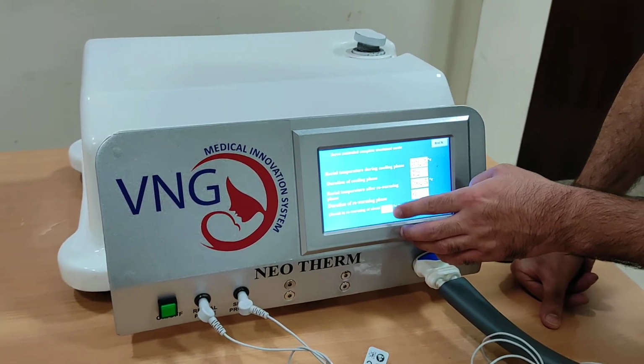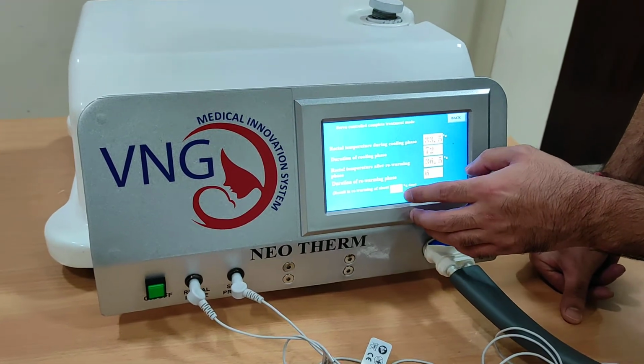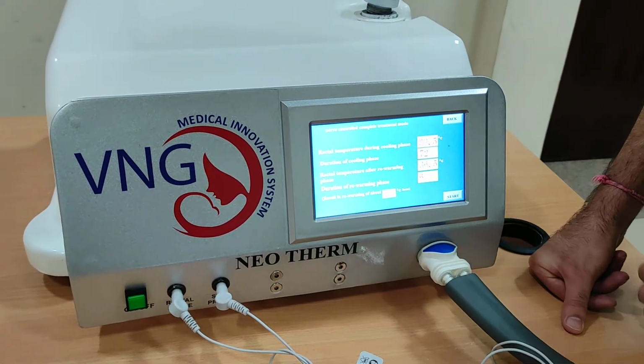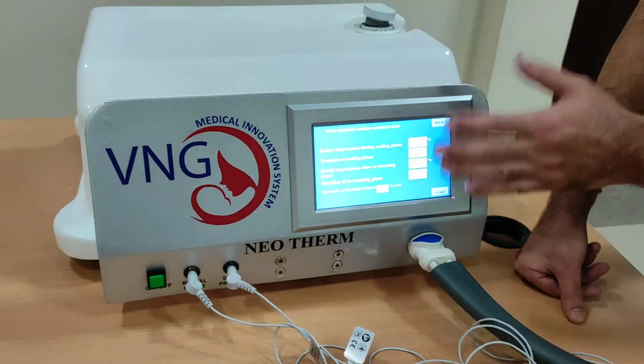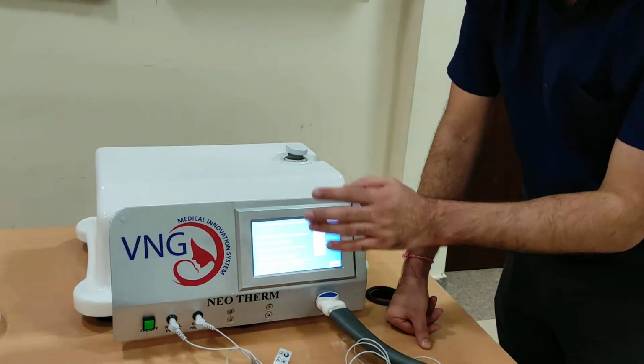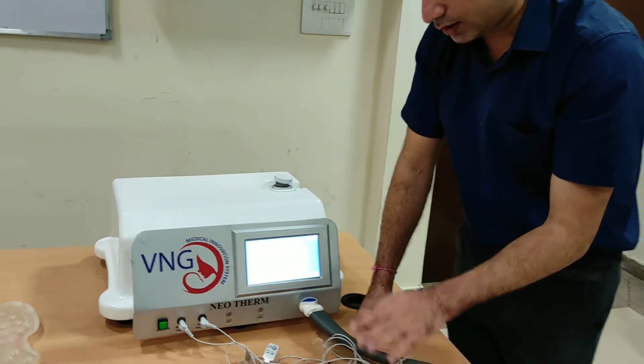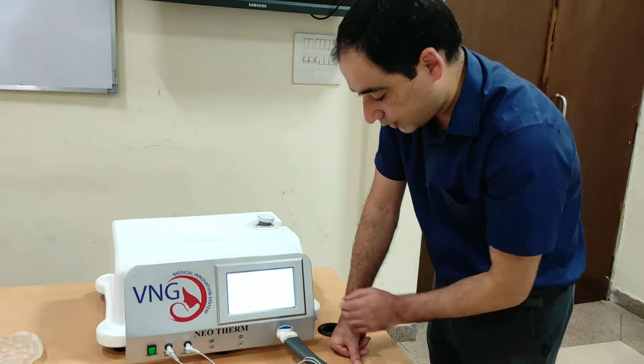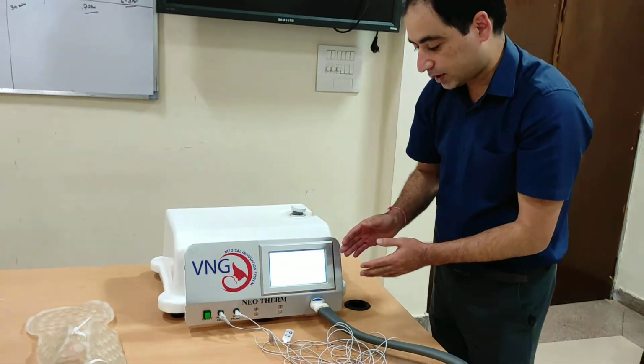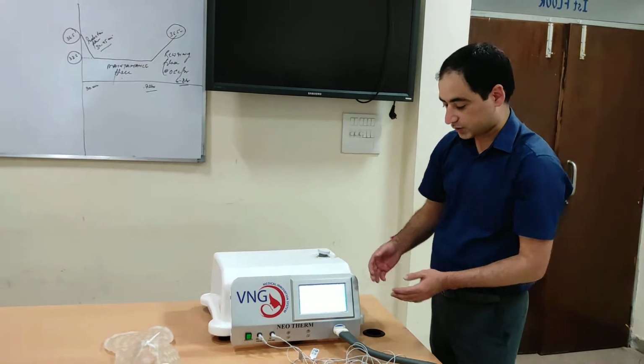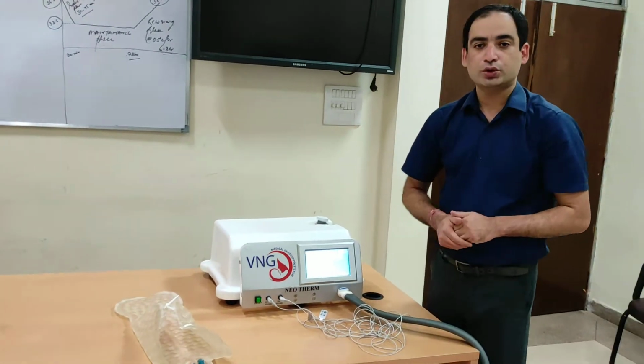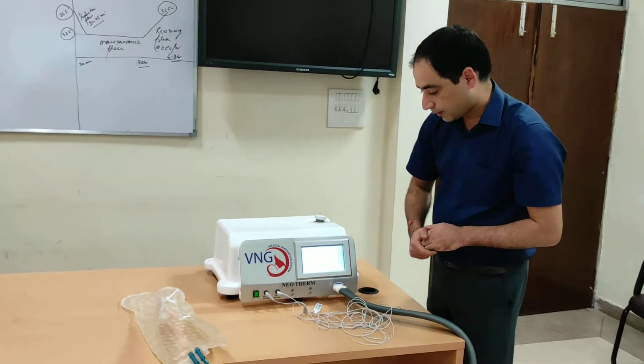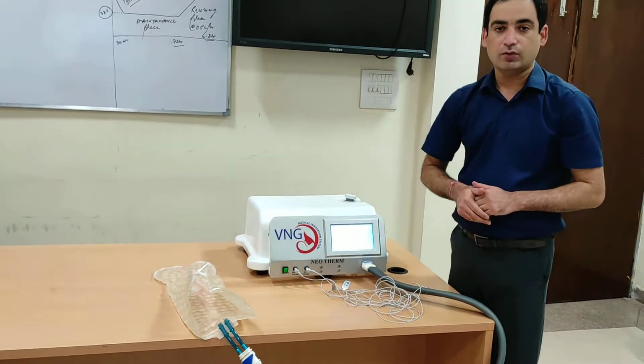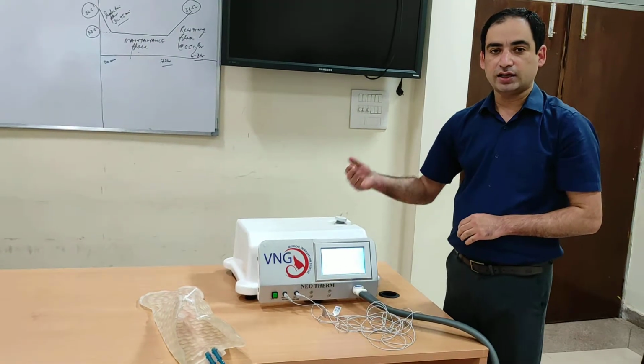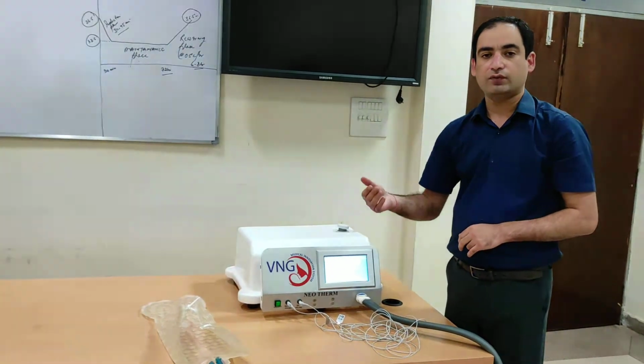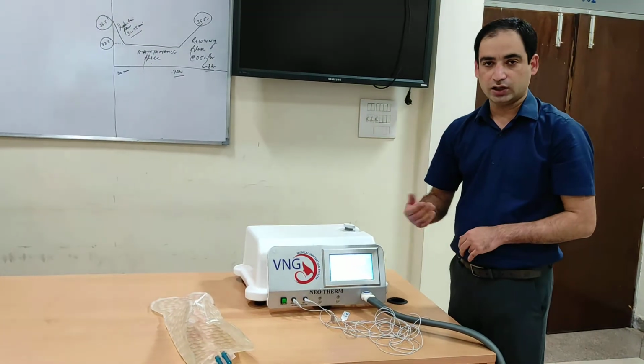You can see here that the machine has automatically calculated the rewarming, that is, it will be at 0.5 degrees Celsius per hour. So once we have set these 4 settings and the baby is inside the jacket, rectal probe is in situ, then we should start this therapy. Once you start the therapy, all the temperatures, that is the rectal temperature, skin temperature, will be displayed on the main screen. It will also show you the duration of therapeutic hypothermia, and there will be graphical representation at the bottom of the screen. Within 10 minutes, the graph will start appearing and it will give you constant measure of rectal as well as skin temperature after each hour.